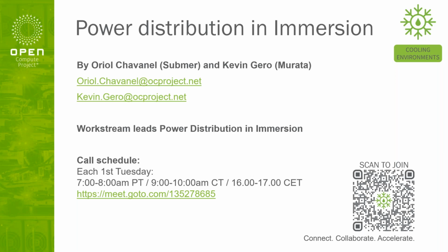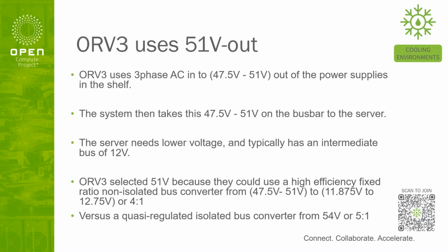During the last couple calls, we've been talking about power in immersion, so connectors and the amount of power they can handle in immersion fluid versus air. We're typically utilizing the same parts used in air, and in fluid we find that the connectors, especially the power clip, can handle about twice the current with the same temperature rise. One of the things I've brought up is the differences between 54 volt and 51 volt in that same temperature rise.